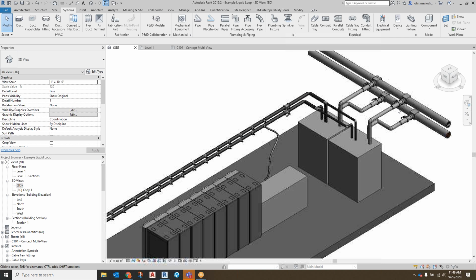Yeah, I agree with that, I suppose. You're saying those big boxes on the right, whether it has a CDU or a heat exchanger, is a critical design consideration, right? And by the way, when I mentioned recommendations as far as KW relating to pipes, I wasn't necessarily talking about one or the other, either a primary loop or a secondary loop, or a case where the whole loop is the primary loop, for example if you've got a dry cooler running higher temperatures.